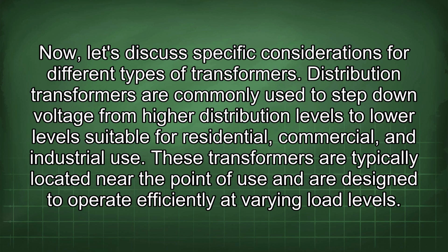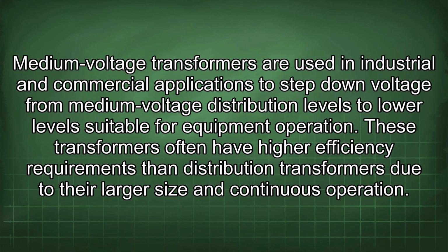Now, let's discuss specific considerations for different types of transformers. Distribution transformers are commonly used to step down voltage from higher distribution levels to lower levels suitable for residential, commercial, and industrial use. These transformers are typically located near the point of use and are designed to operate efficiently at varying load levels. Medium voltage transformers are used in industrial and commercial applications to step down voltage from medium voltage distribution levels to lower levels suitable for equipment operation.